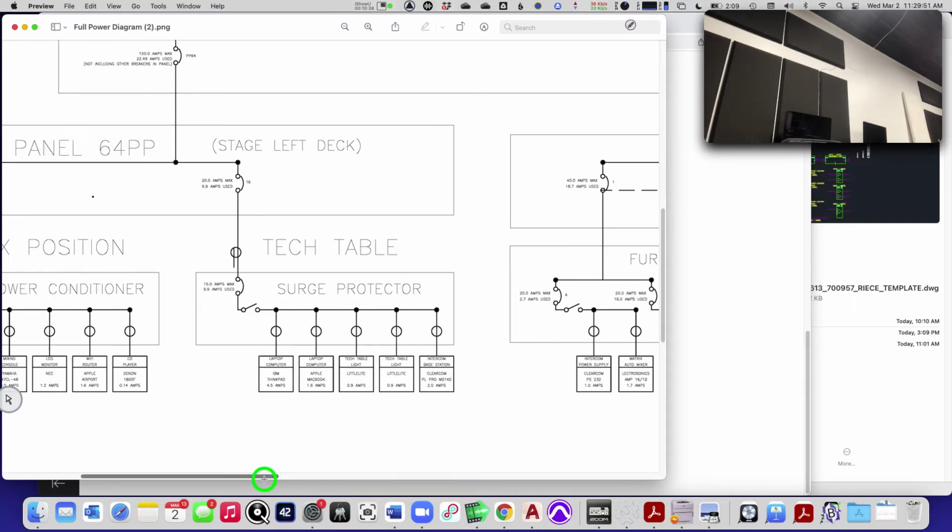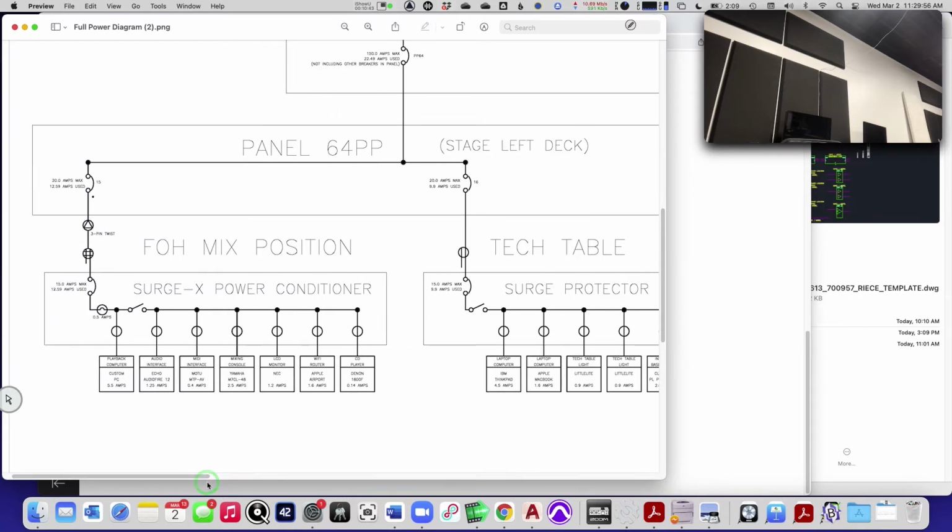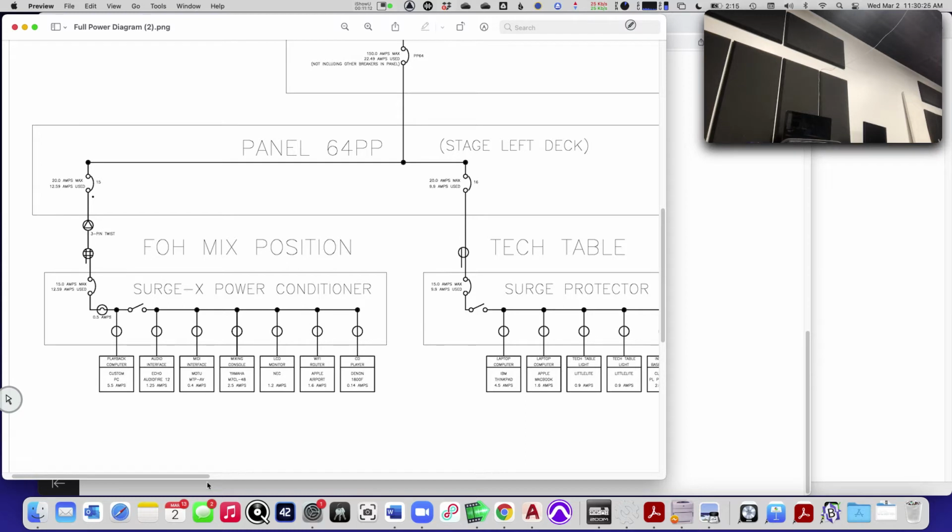And that goes into this big one here, the 150 amp one. What I wouldn't want is for this to be 175 amps, because then I could potentially pull 151 amps, not break this, but shut the whole building down, and everybody else that feeds off it too. So as you go down, closer and closer to the things that plug into the wall, each breaker should get smaller in its capacity. That's an electrical code thing.